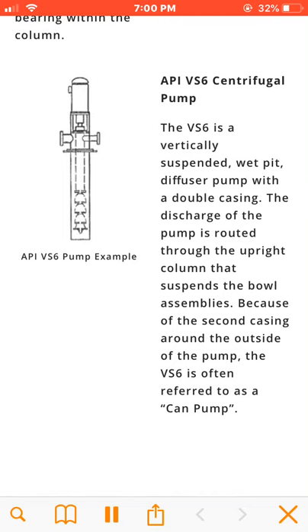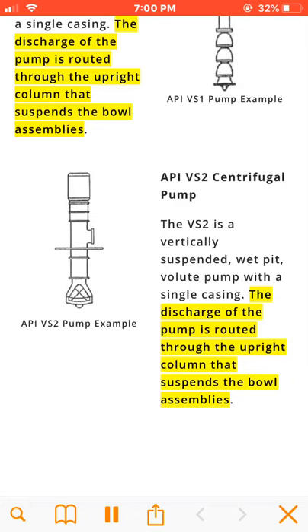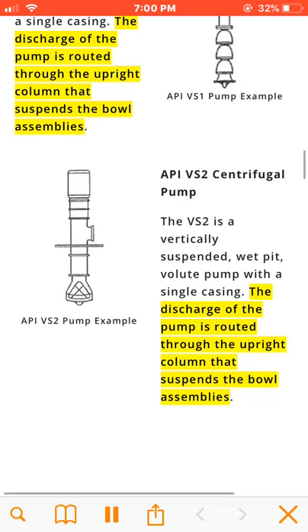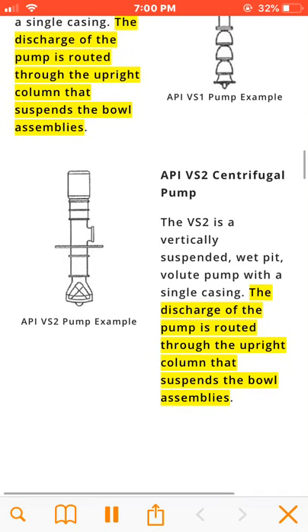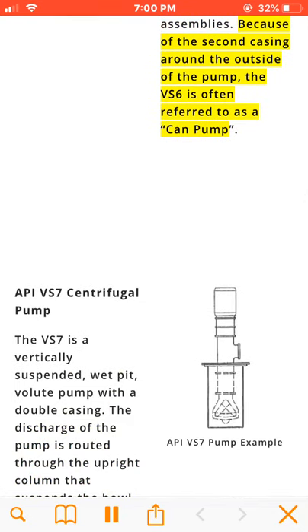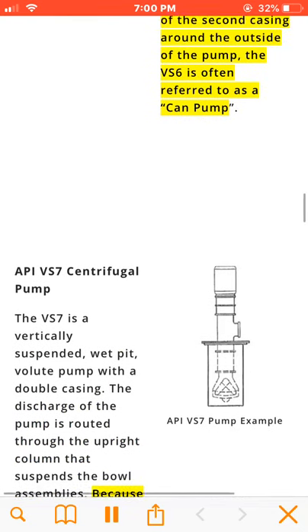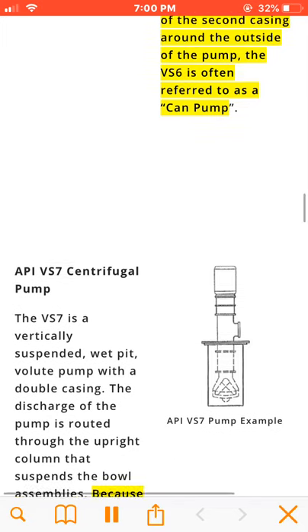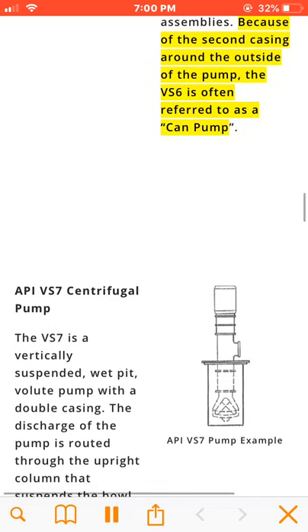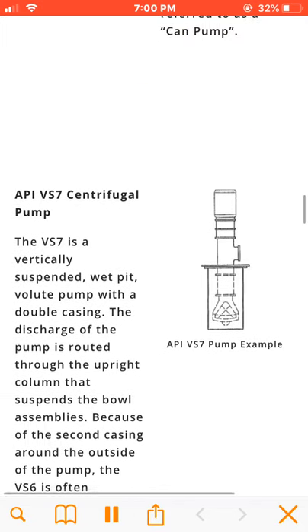The VS6 is a vertically suspended, wet pit, diffuser pump with a double casing. The discharge of the pump is routed through the upright column that suspends the bowl assemblies. Because of the second casing around the outside of the pump, the VS6 is often referred to as a can pump.